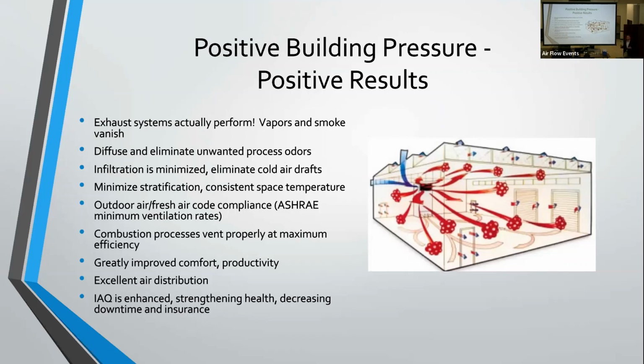So you're really getting an exhaust system plus a secondary exhaust system by pressurizing that space and pushing that air out. Also, if you're pushing air outside through the openings of the building, you're minimizing infiltration in that space. So you're reducing those cold drafts and cold spots that make employees uncomfortable, and you'll see increased productivity because the employees are more comfortable.